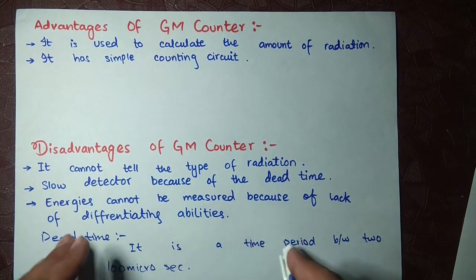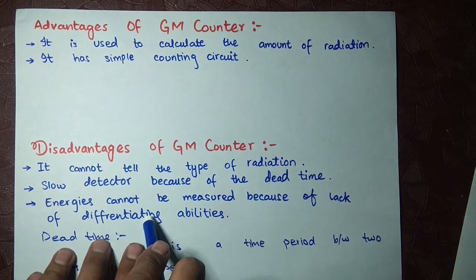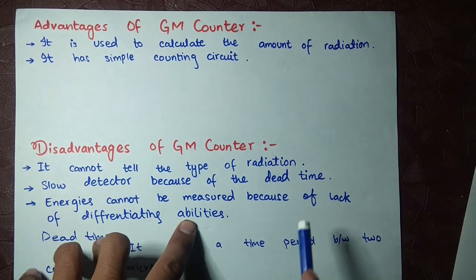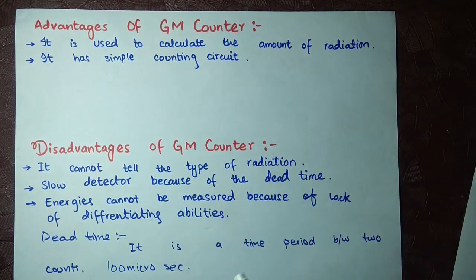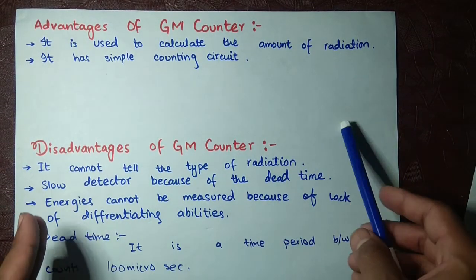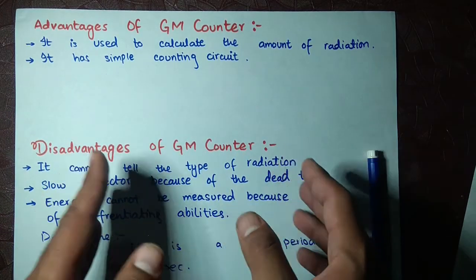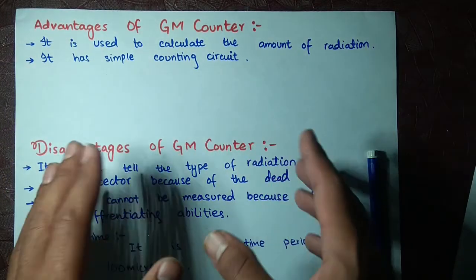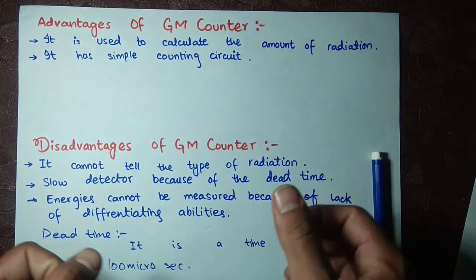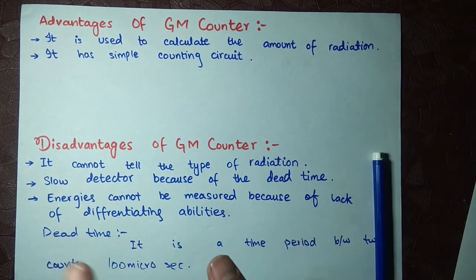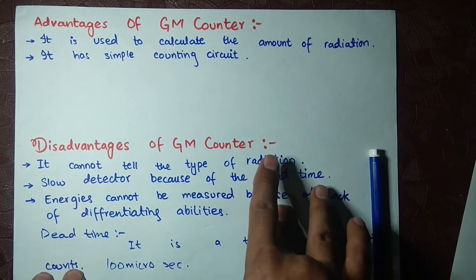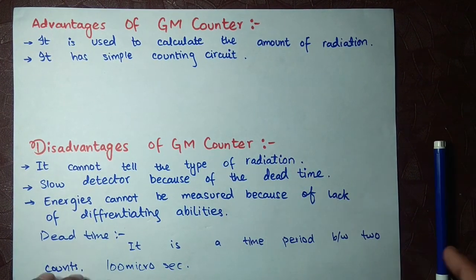Another disadvantage of the GM counter is that energies cannot be measured because of its lack of differentiating ability. A beta particle with higher energy than gamma cannot be distinguished — it makes a pulse with more electrons and more energy, but we only get one pulse. We cannot say whether it is beta or gamma or what energy it has.